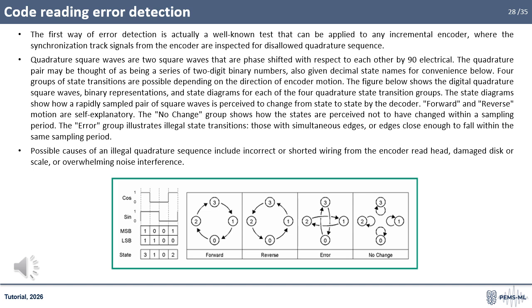The first way of error detection is actually a well-known test that can be applied to any incremental encoder, where the synchronization track signals from the encoder are inspected for a disallowed quadrature sequence. Quadrature square waves are 2 square waves that are phase-shifted with respect to each other by 90 degrees electrically. The quadrature pair may be thought of as being a series of 2-digit binary numbers, also given decimal state names for convenience below. 4 groups of state transitions are possible, depending on the direction of encoder motion.